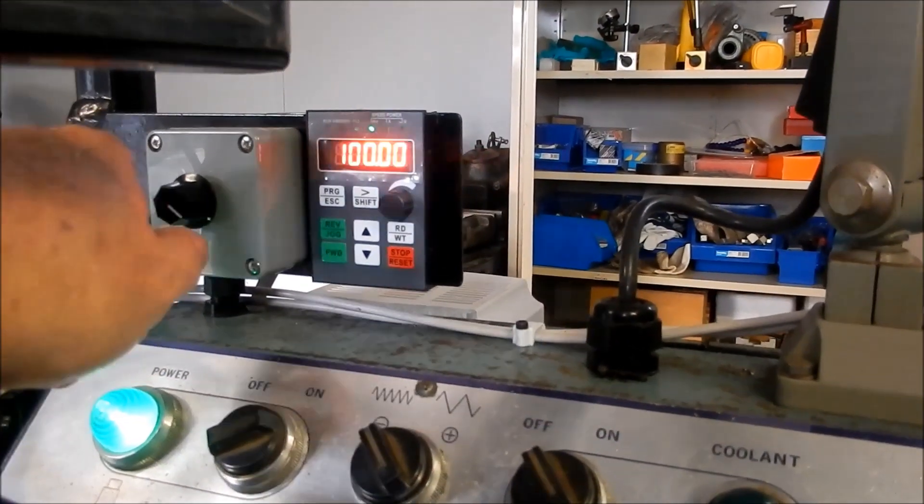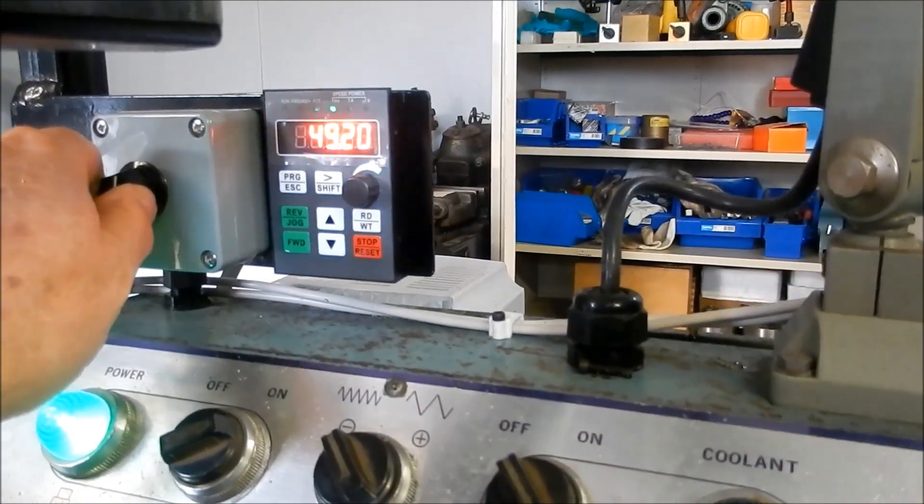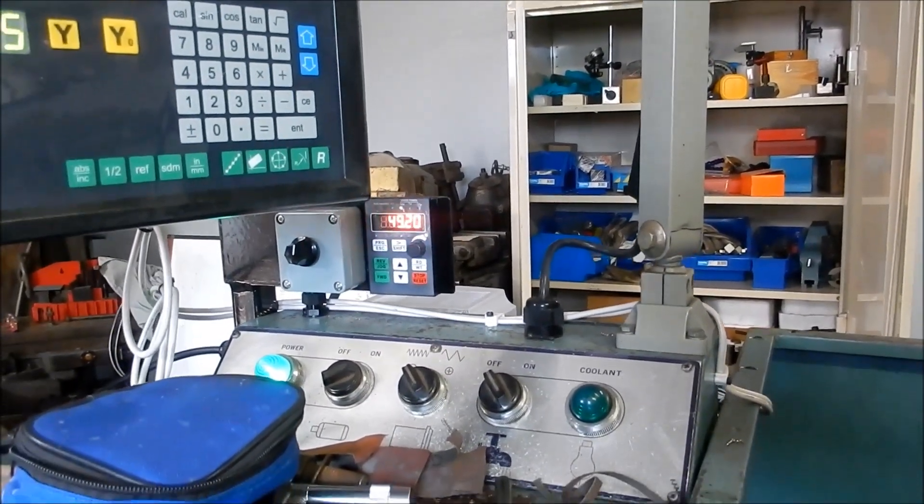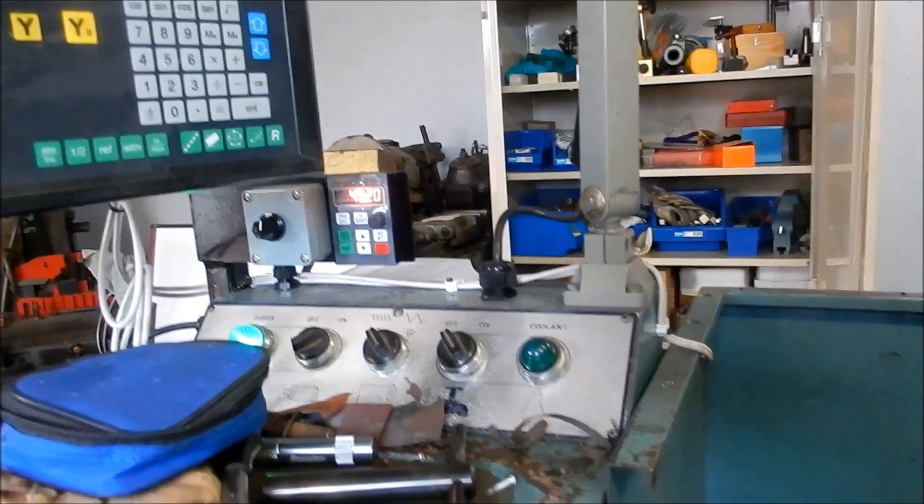Let's go to 50 Hz. Can't get quite under 50 Hz — that's the closest we can get. We should be running at 900 RPM.